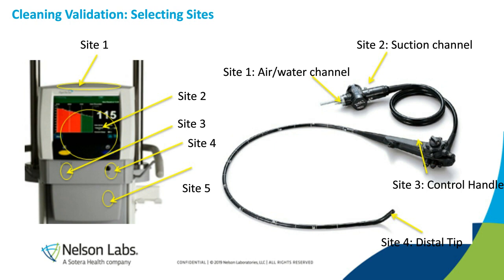And this would include testing different points, for example, the air-water channel, the suction channel, the control handle, and the distal tip. Now the difference is for these 2 devices, for a piece of equipment, we may be able to choose the worst case area of that device and adopt all the other parts of that device in that cleaning disinfection adoption. Now for scopes, current requirements require all the parts to be tested separately. So we need to test all the sites separately and have results for all of those sites.